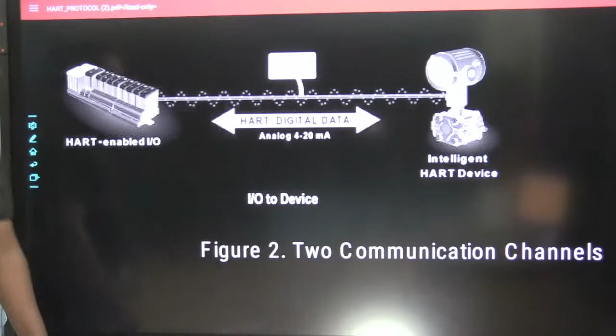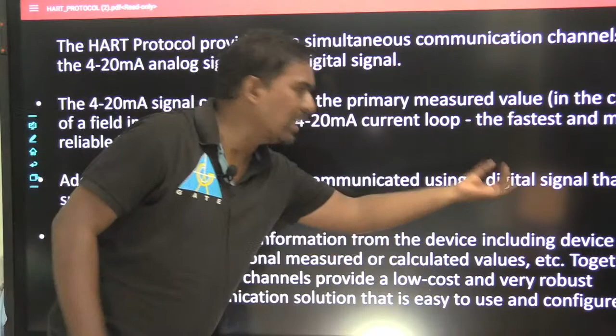So, before this, I want to show one point. The HART protocol provides two simultaneous communication channels. One is a 4 to 20 milliamperes signal, the other one is a digital signal. The 4 to 20 milliampere signal communicates the primary measured value using the 4 to 20 milliampere current loop, the fastest and most reliable industry standard already there. Additional device information is communicated using a digital signal.